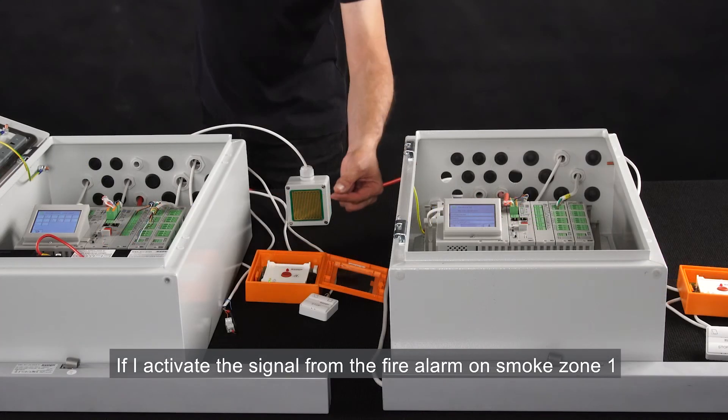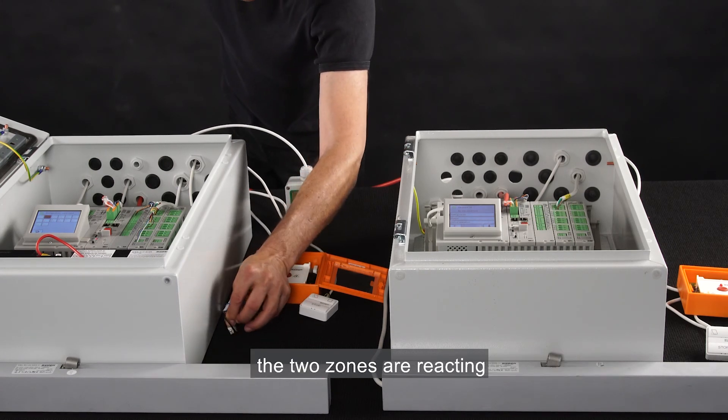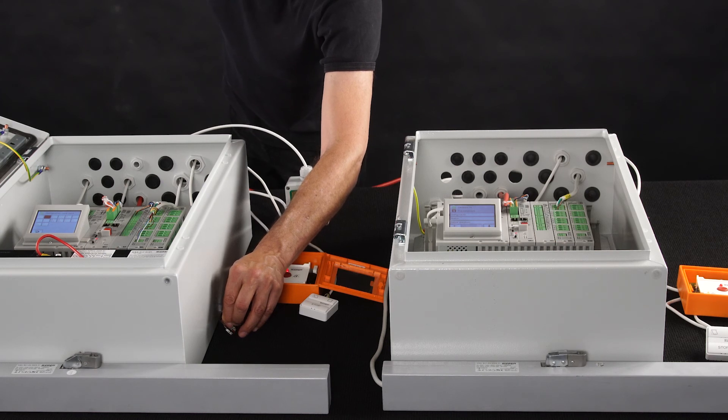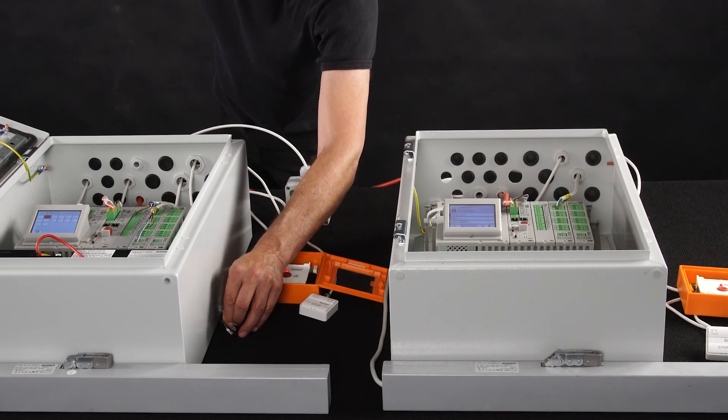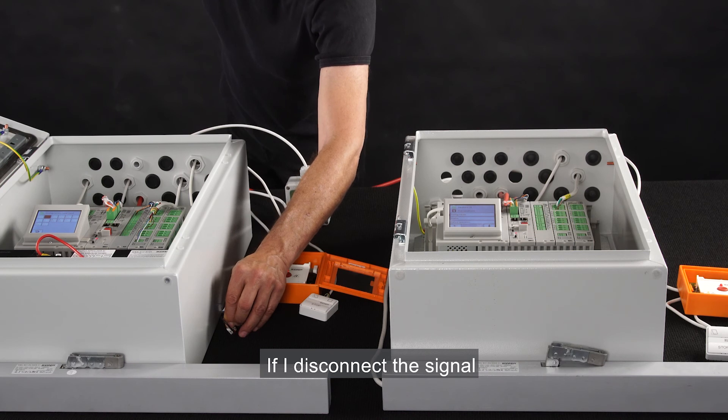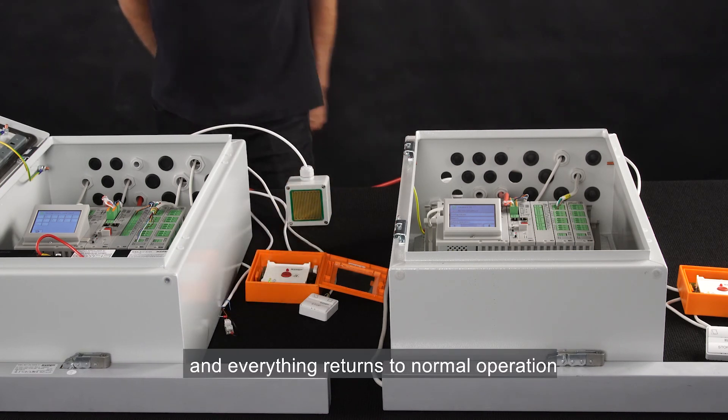If I activate the signal from the fire alarm on smoke zone 1, the two zones are reacting. If I disconnect the signal, the actuators are closing, and everything returns to normal operation.